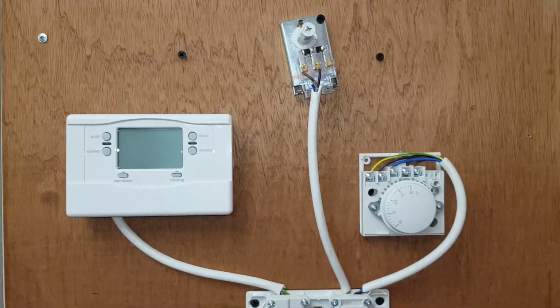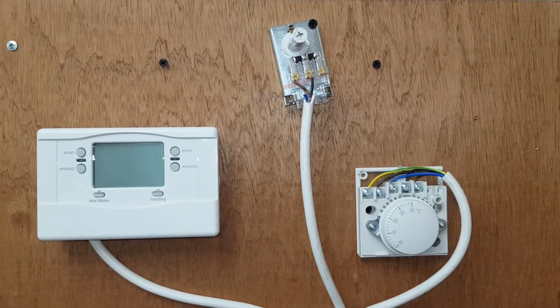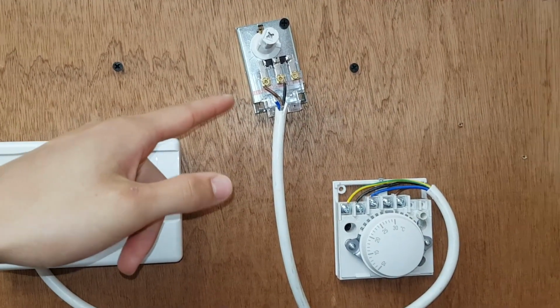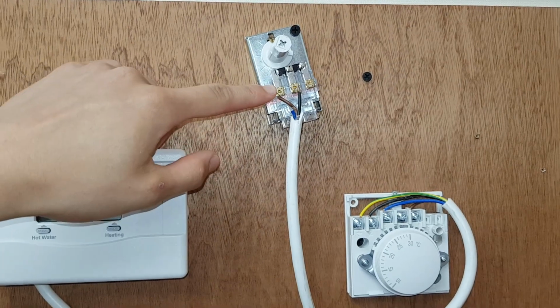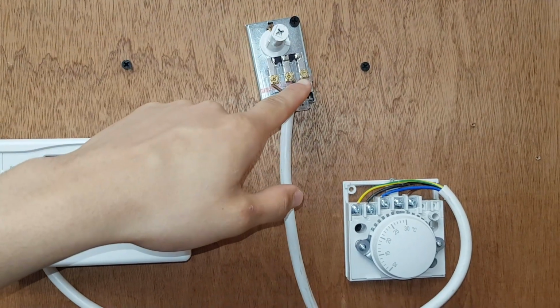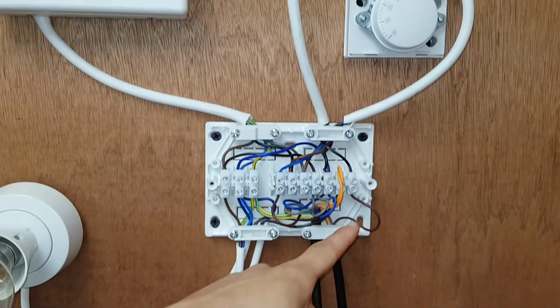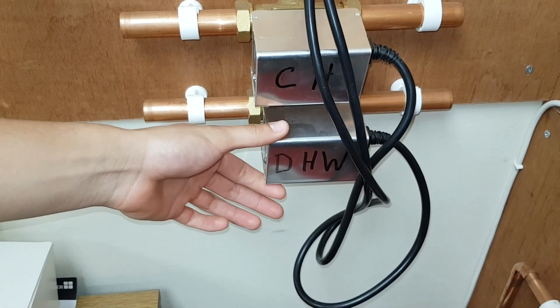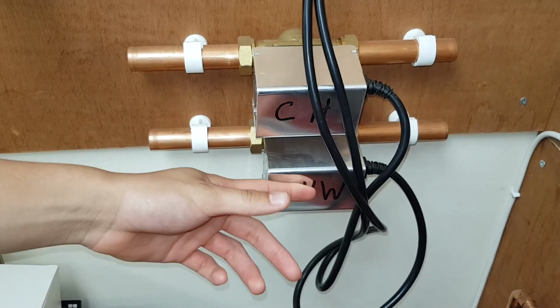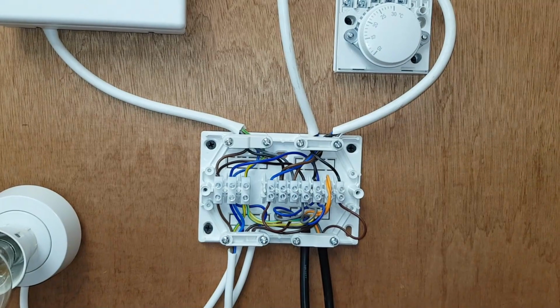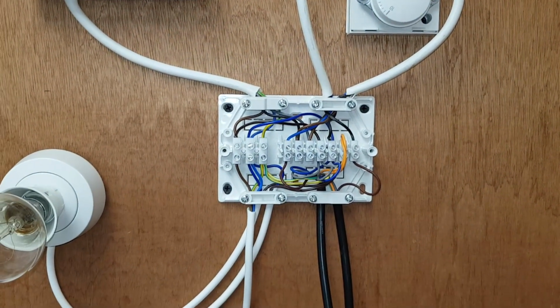Where does it flow? Right, so from terminal 3, it comes up to your cylinder stat this time on the common, which then makes a switch over to terminal one. Coming down to live here, activating the motor in your hot water zone valve, which creates a micro switch coming up onto your orange, starting the pump and boiler. That's it.